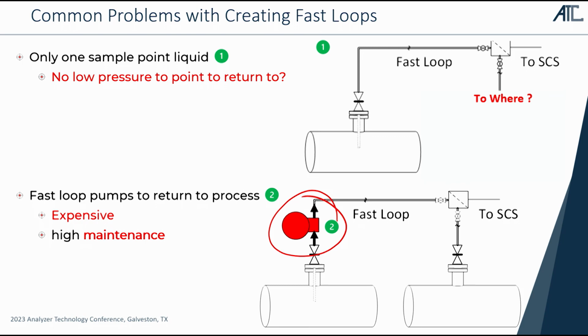They're fixing the pumps all the time. There's going to be a sizing issue. We had a meeting this week talking to some people, and they said the problem was they oversized the pump, and it was cavitating on the inlet side. So who's going to do the sizing for the pump? Did it get sized properly for my application?